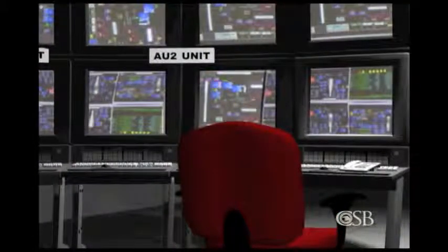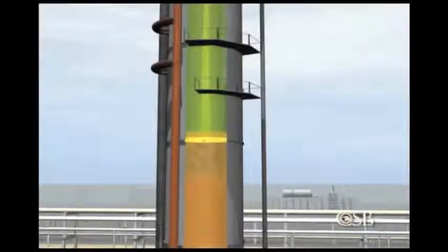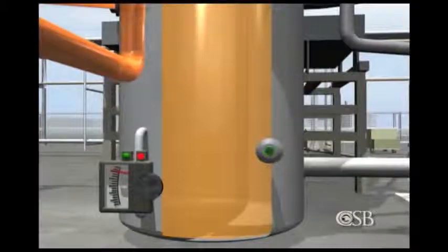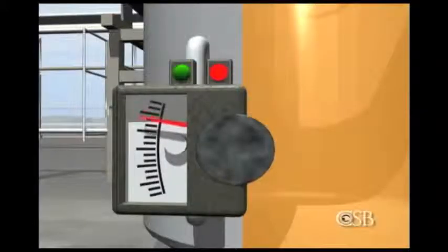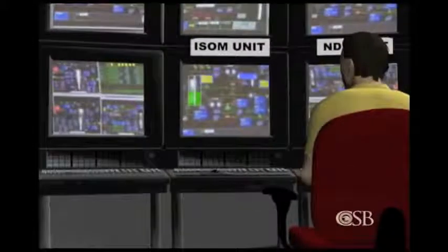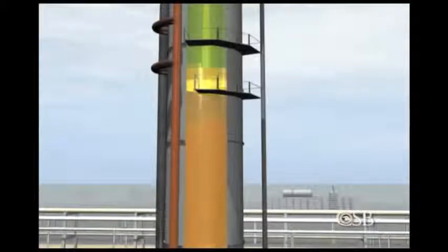As the startup continued, the tower steadily filled with liquid, reaching a height of 98 feet shortly before noon, more than 15 times the normal level. But the improperly calibrated level indicator told operators in the control room that the liquid was at 8.4 feet and gradually falling. Furthermore, the control panel was not configured to clearly warn operators of the growing danger. It did not display flows into and out of the tower on the same screen, nor did it calculate the total liquid in the tower.